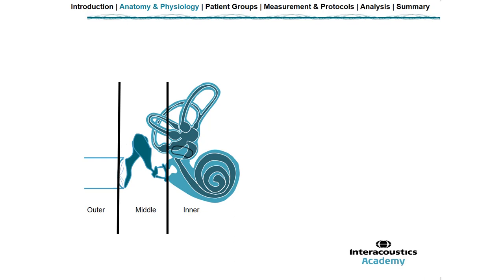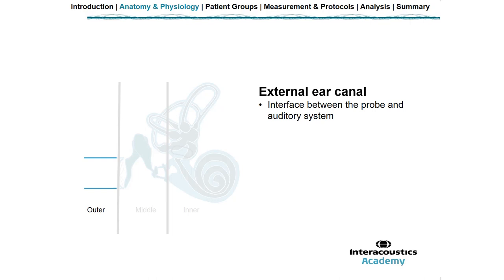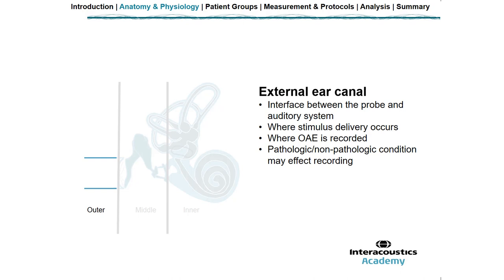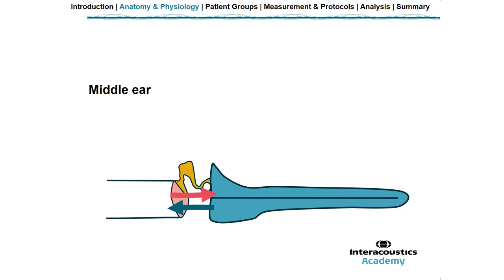Now let's look at the role the outer, middle, and inner ear play in recording an OAE. The outer ear or external canal is where the interface is between the probe and the auditory system, where stimulus delivery occurs, and where we're recording the OAE. Any pathologic or non-pathologic condition will affect our recording, so we need to consider things such as wax or debris, the shape of the ear canal, and ensuring a good probe fit. If the probe is not fitted properly, there can be leakage of the OAE and environmental noise can enter the recording.